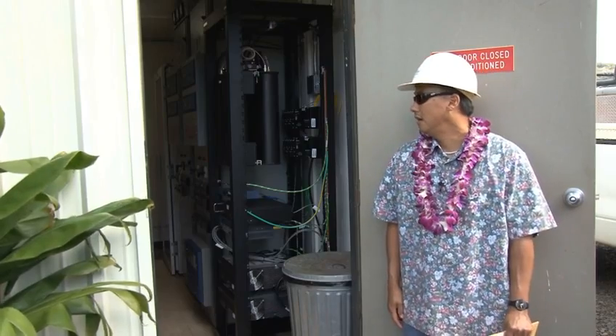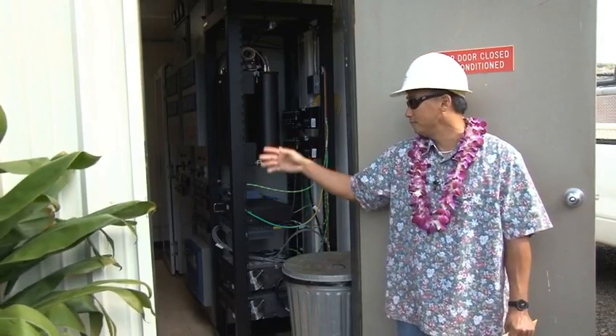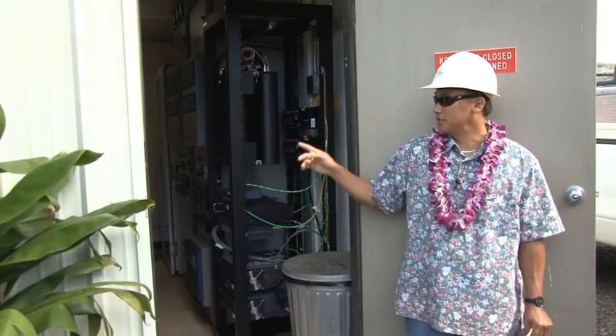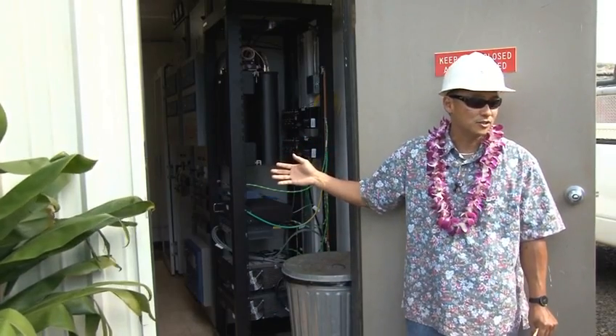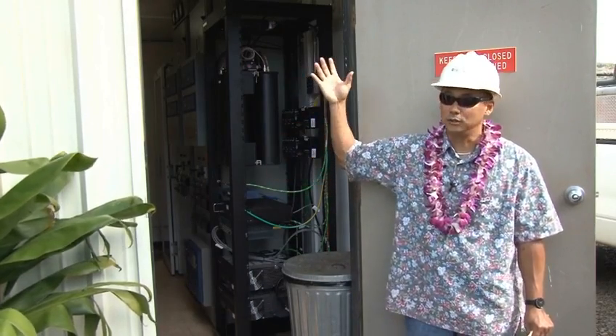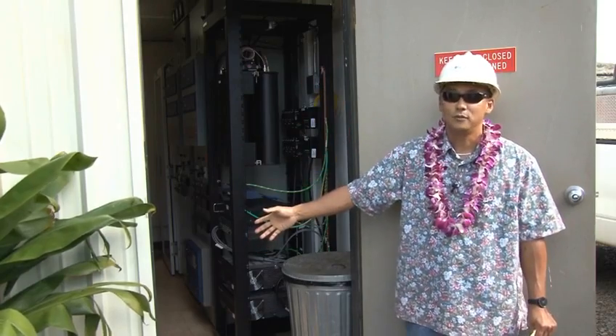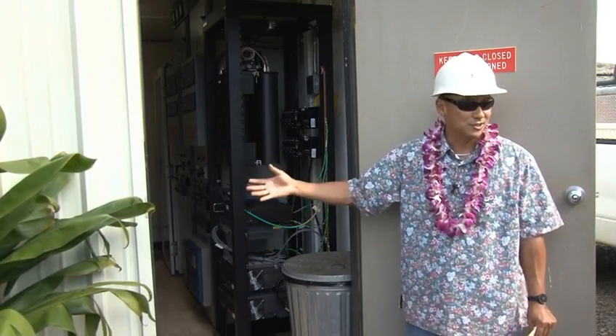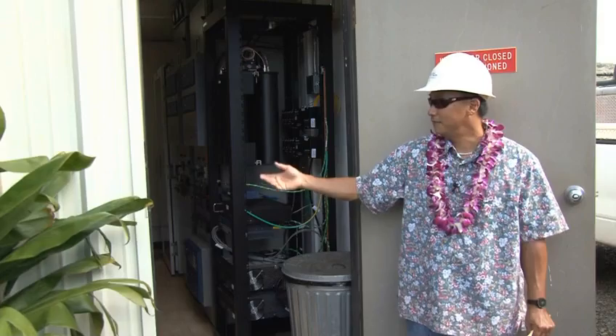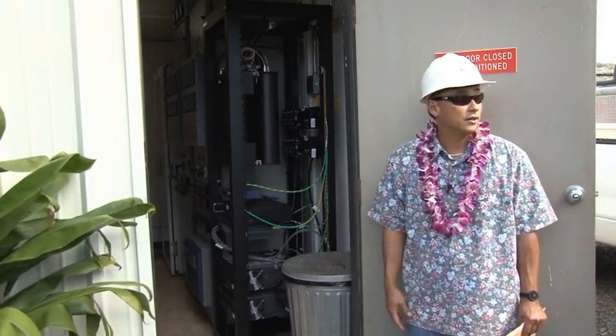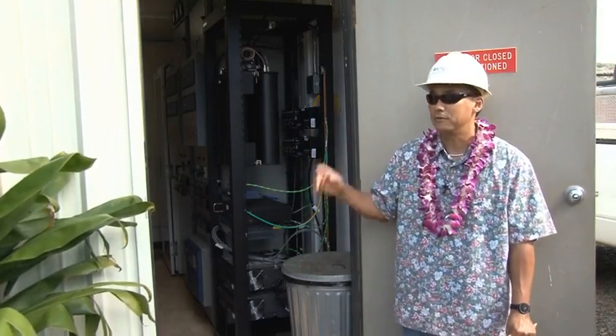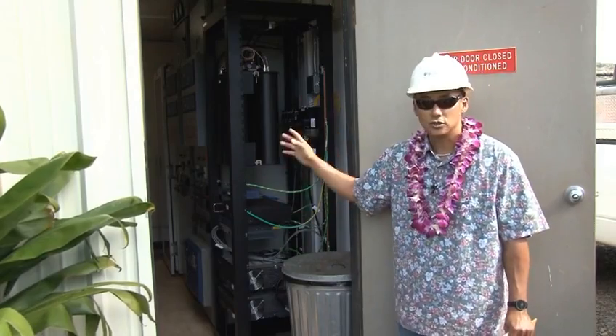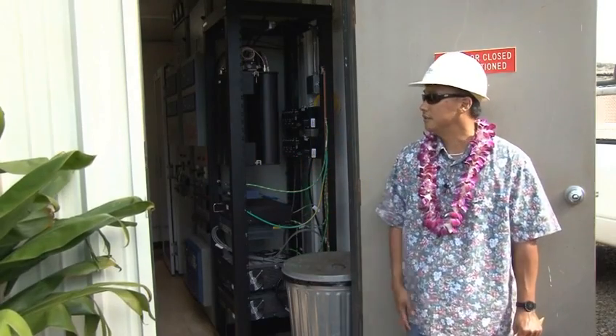So this control room, and if you come in later on, you can see there's batteries in here, actually. Because obviously when you lose power to this whole station, we need to know that power is out of this whole station. So the communication devices are all backed up with battery also in here that keeps the 48 DC power up and running. So all the equipment, electronics, and computers can still continue to run.